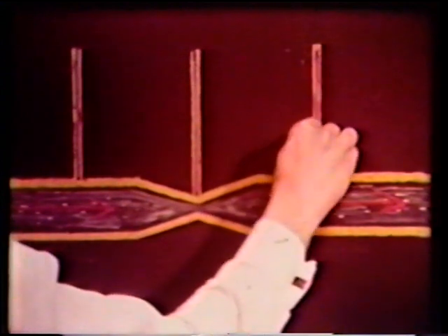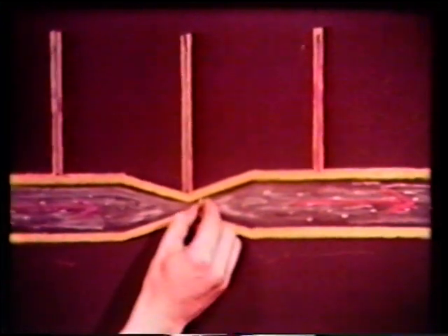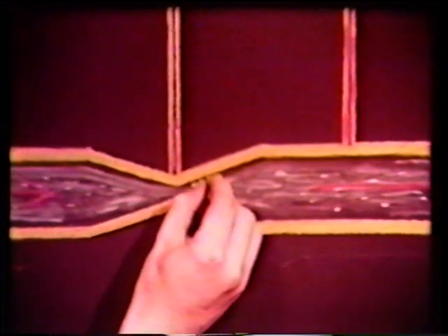When the minimum pressure is low enough, vapor cavities are formed. As these pass into the region of rising pressure, they collapse. If the rate of pressure rise is high, then their collapse is violent.